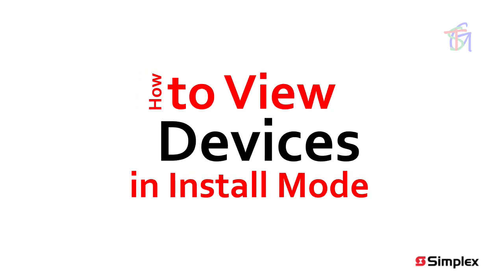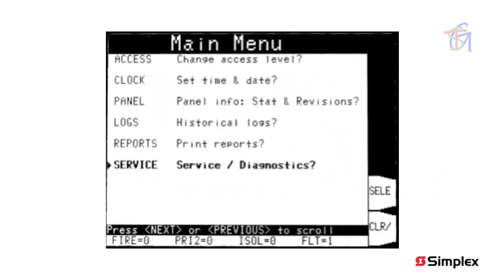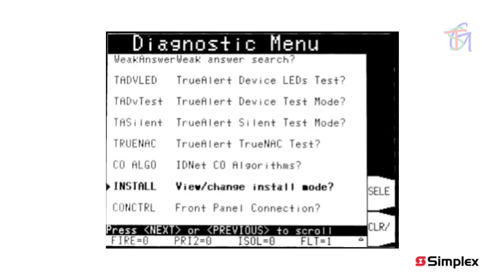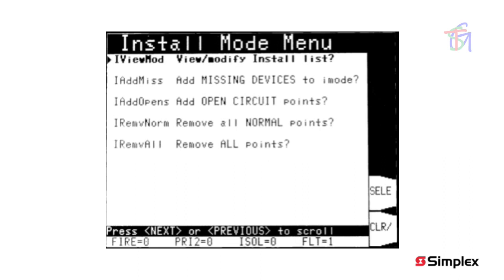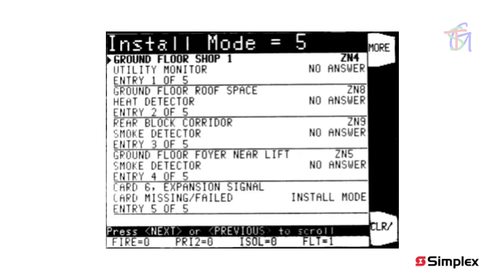To view devices in install mode, press menu, then scroll the highlight to the service or diagnostics option and press the select soft key. In the diagnostic menu screen, scroll down to the install mode option, using page down to jump a screen at a time. Press the select soft key to select it. The contents of the install mode list can be viewed with the view option of the install mode menu. Viewing this menu does not require being logged in. The install mode display shows the device count and a list of devices and modules with their current status. The more soft key will provide more info for the highlighted entry in the list.